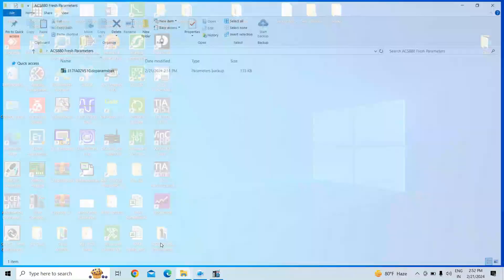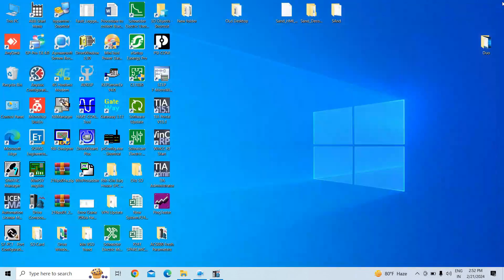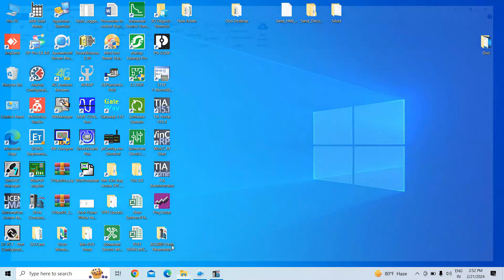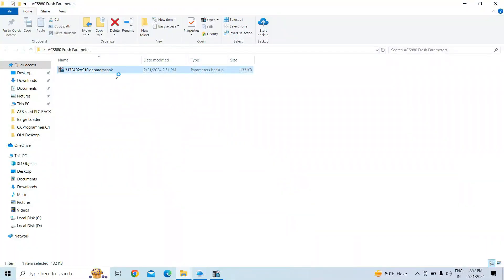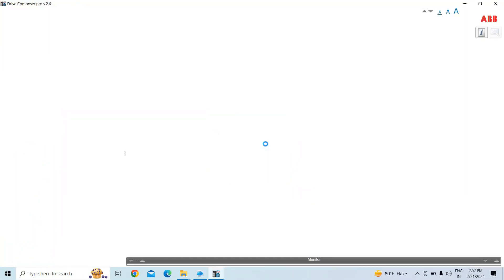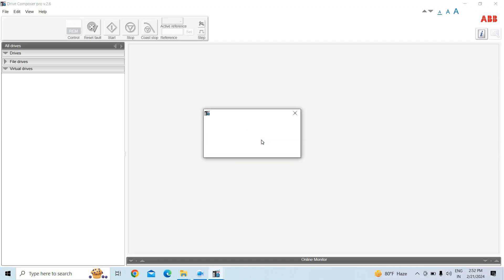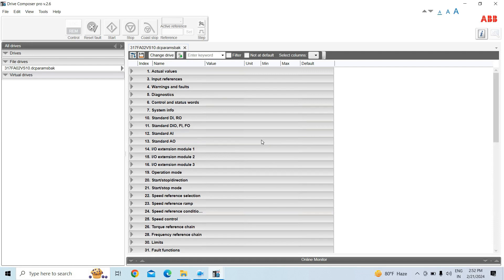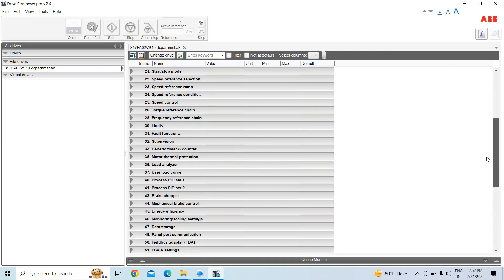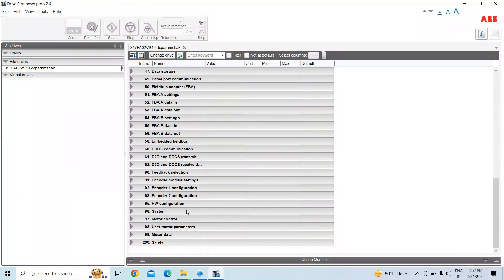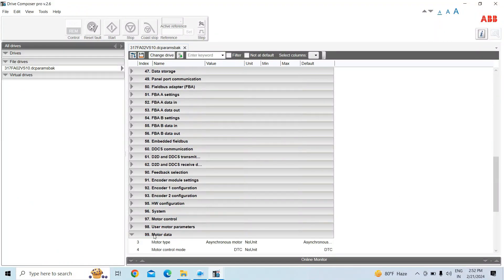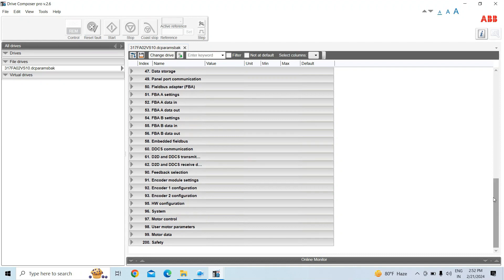The parameter is saved. You can see it in that folder. Now we will close and open that backup parameter file. We will change some parameters and reload them to the drive. In parameter group 99, this is the backup file.